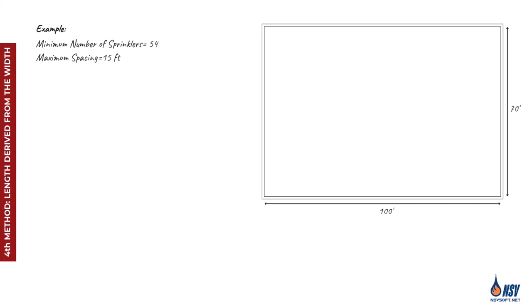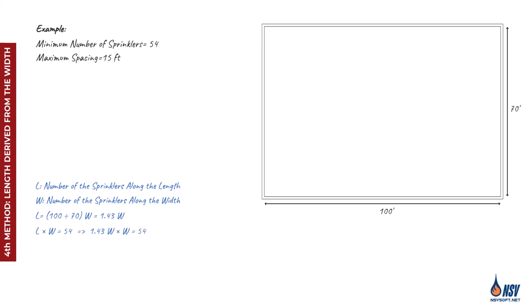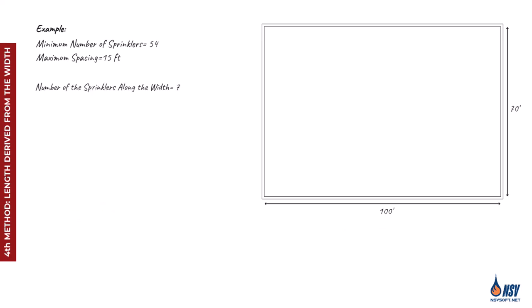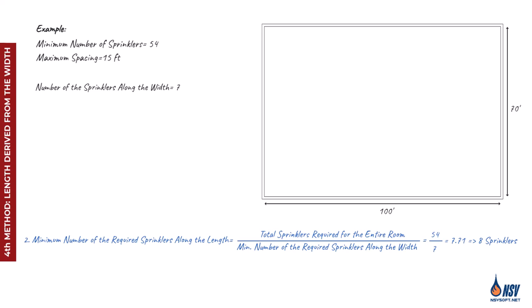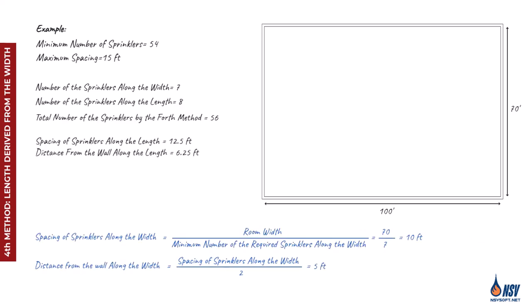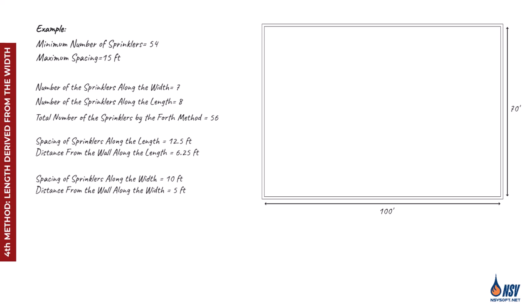The fourth method is similar to the third. In this approach, L is defined in relation to W where L equals 1.43 times W. By replacing L and solving the equation, we find that W equals 7 sprinklers. The remaining steps are the same: determine the number of sprinklers along the length by dividing the total by W, calculate spacing and distance from the walls along both directions, and position the sprinklers in the layout starting from a corner and maintaining consistent spacing.